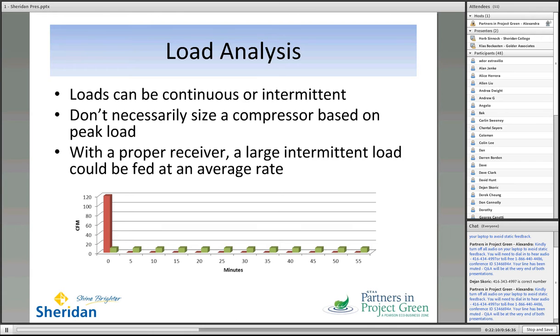And the final points I would like to make are that maintenance is really critical to this peak performance. I'm sorry, it looks like I've lost a connection to the network. So covering maintenance items, the key ones would be maintaining the lubricant level, so inspecting that on a daily basis, draining the receiver and the drop legs and traps so that you avoid water buildup, visually inspecting your system, looking for leaks, looking for noise and vibration, safety covers that are off, belts that look wrong. And really probably key is turn off and disconnect your power at the end of the day so that you're not running that 24/7, 365 kind of schedule.